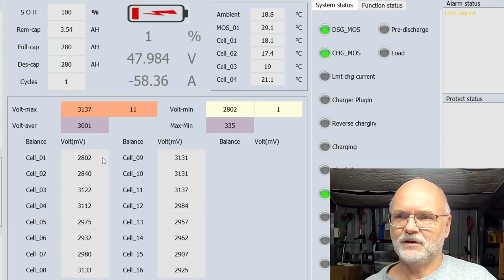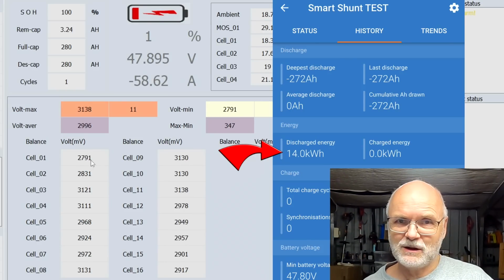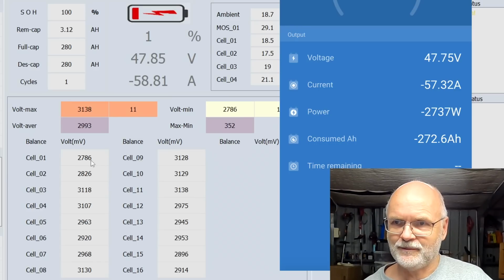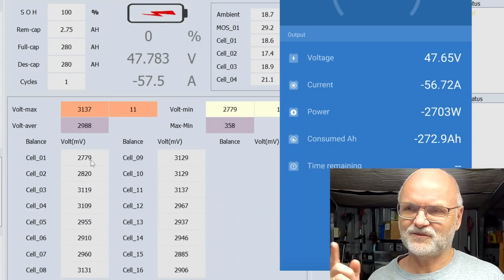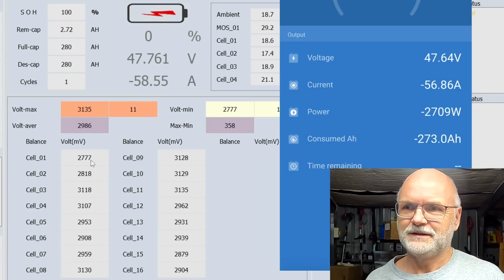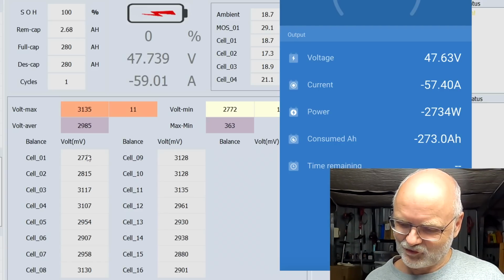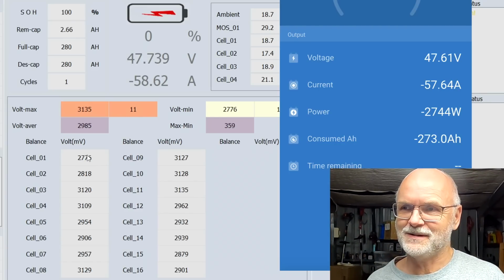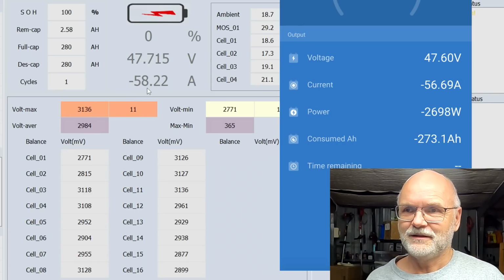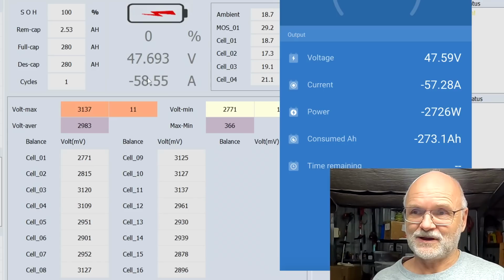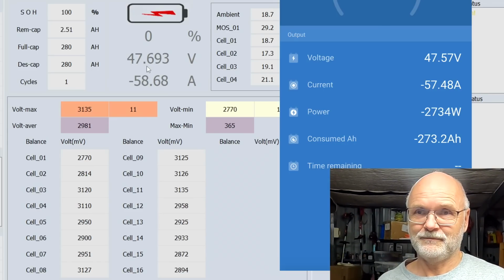Okay, back to serious. Under 2.8 volts, 14 kilowatt hours, 272.6 ampere hours we have pulled. I can hear the fans are spinning down on the inverter now - it's getting hard to maintain the 2.7 kilowatt the Tesla demands. We're almost at 60 amps now - voltage goes down, amps are going up, power stays the same.